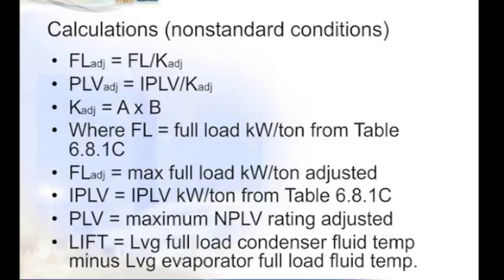Where does full load value come from? Well, it comes from Table 6.8.1C, as does the integrated part load value, both of those being in kW per ton. What is lift? Lift is the leaving full load condenser fluid temperature minus the leaving evaporator full load temperature. The key words here are full load, which are essentially the same as your design conditions that you want that chiller to operate under at a maximum condition.